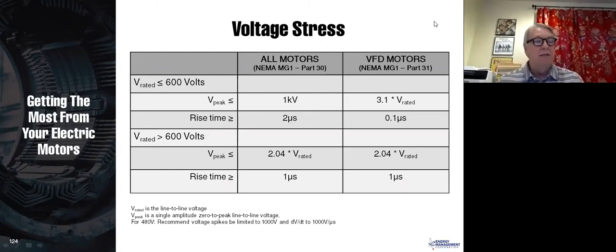All right, now I've talked a lot about MG1, and you're saying, what is that? Well, NEMA, the National Electrical Manufacturers Association, has a standard for motors. Their standard for motors is MG1, and Part 30 of MG1 is for all motors. Part 31 of MG1 is for variable frequency rated motors. Now you'll notice that all motors should have 1 kV insulation. There are several insulation levels. For instance, you know that a motor by NEMA standards is rated for twice line-to-line voltage plus 1,000 volts. That's a rating for surges. This is a rating for outputs of variable frequency drives.